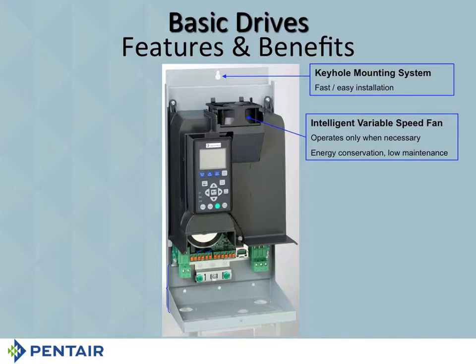The only time I know for a fact that you will hear that fan, though, is if you wind up with a low voltage fault, because low voltage will turn the drive off, and once the drive gets turned off, you wind up not having any voltage. So it says, hey, we need to get rid of the energy that's on the capacitor pack. So when the voltage goes down, the fan turns on, it pulls all the energy off because the pump has now been turned off.